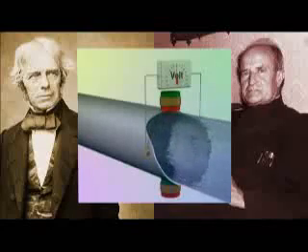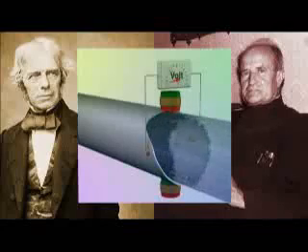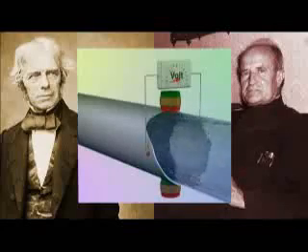The voltage is directly proportional to flow velocity and increases with flow rate. The transmitter converts the induced voltage into normalised analogue and digital signals. Broadly speaking, this principle of electromagnetic flow measurement can be applied to all electrically conductive fluids.